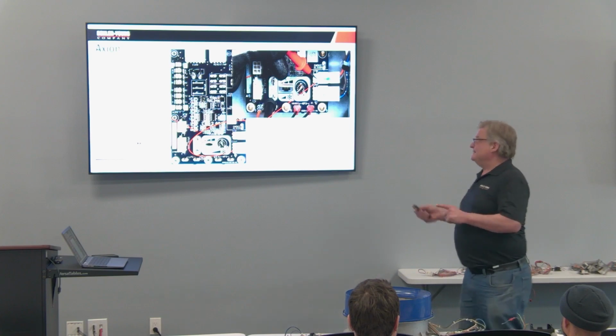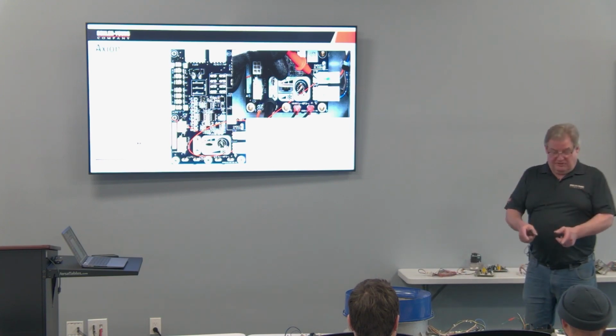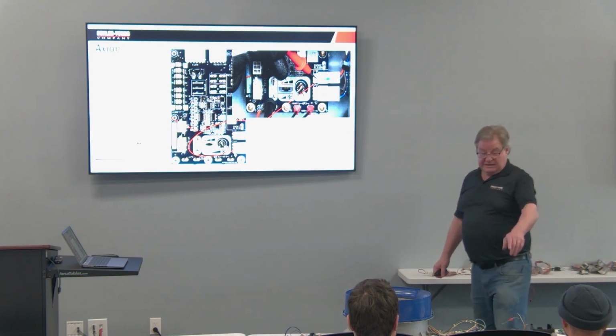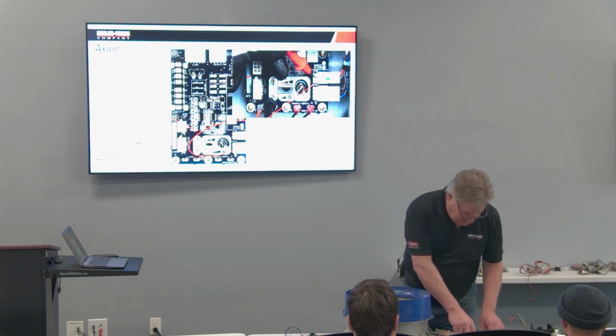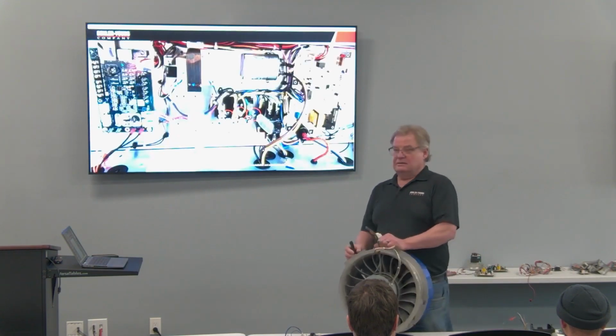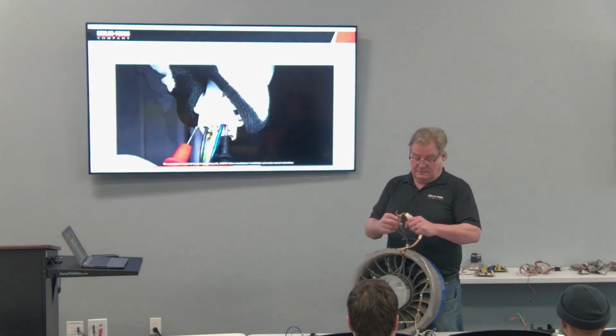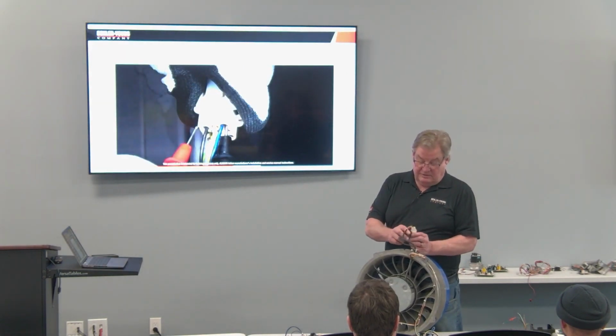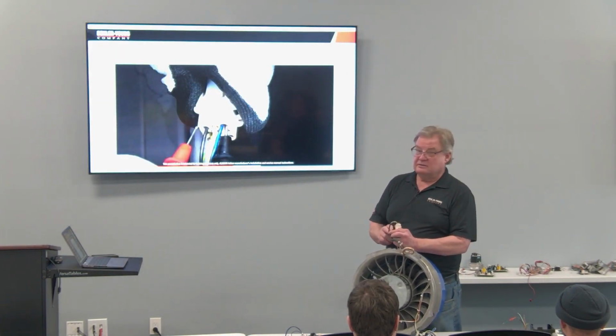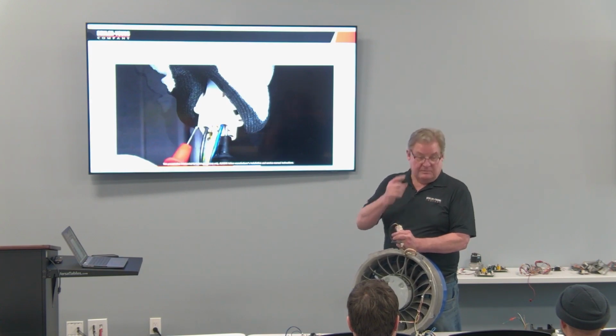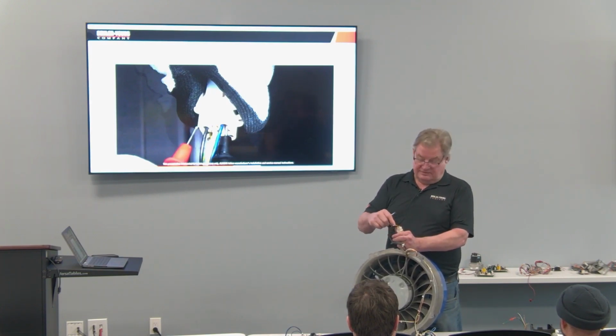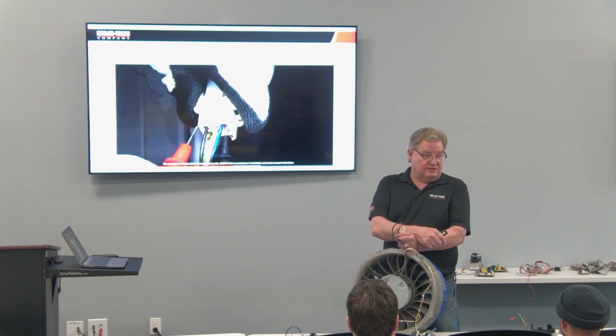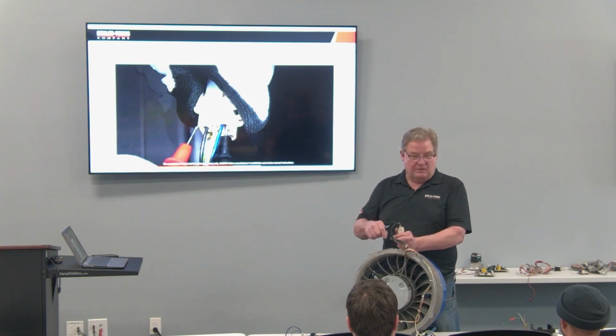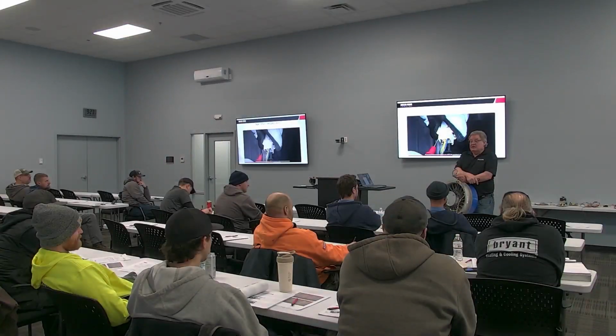So the next half of that test is motor's on, meter on DC. I'm going to again start at the plug here, and there you can see the orange, gray, and white wires. I'm going to take my meter. Again, the white, which you think of as negative, so I'm going to go from white to orange. I should have 10 volts DC if the motor is powered. We just checked it, right? It's 230 at the motor. Then I should have 10 volts between orange and white. If I don't have 10 volts, the motor could be locked out.